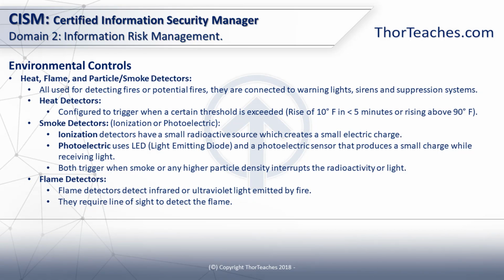For our fire suppression and our fire detection, we use different sensors, but what they detect and how they detect it can vary. And our fire suppression and our fire detection should obviously be attached to warning lights, sirens, and then the suppression system. A heat detector would be configured to trigger if a certain threshold is exceeded. It's an if-then system. If the temperature rises more than 10 degrees Fahrenheit in 5 minutes, then sound the alarm.